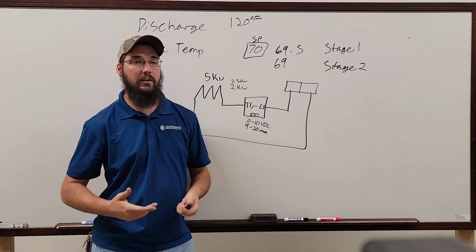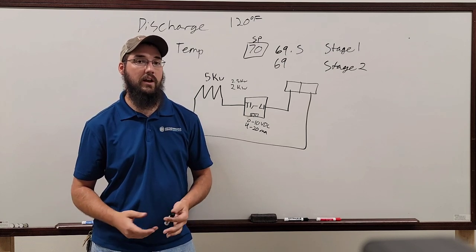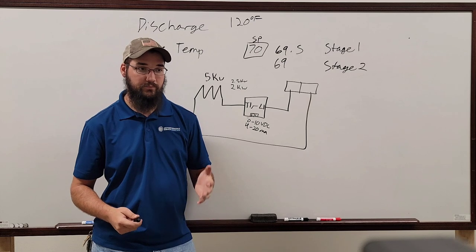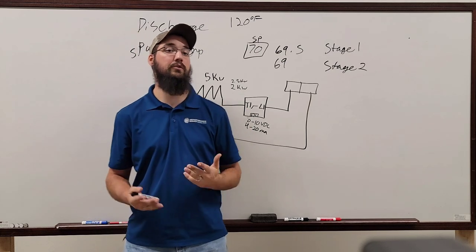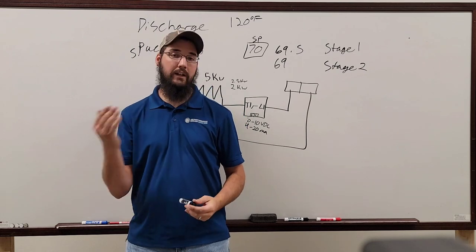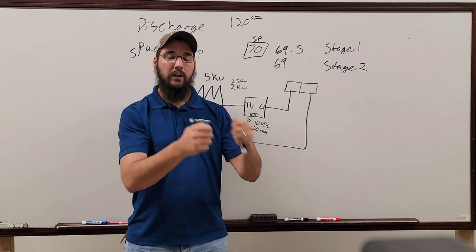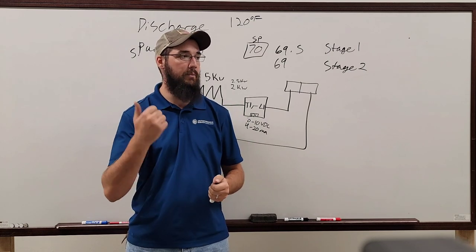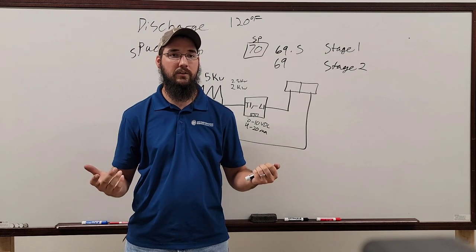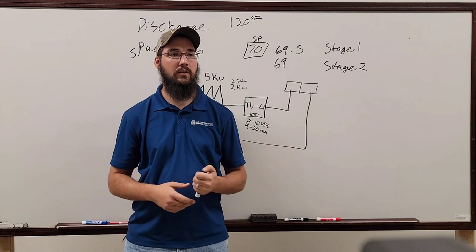You can buy an inexpensive one online that will function just fine, run off of a battery. And you can hook up to one of these. So say you're in the field and you're trying to troubleshoot it, but you can't get the signal from the automation controller that you want to bring it on. Okay, well, disconnect the automation control, hook up your signal generator and ramp it up to see if it comes on. A battery does the same thing on the 0-10 these days.